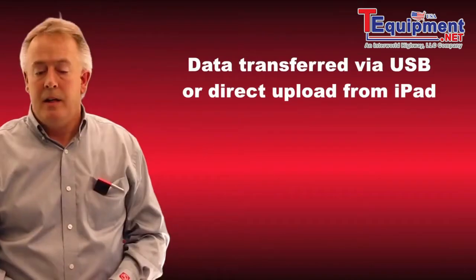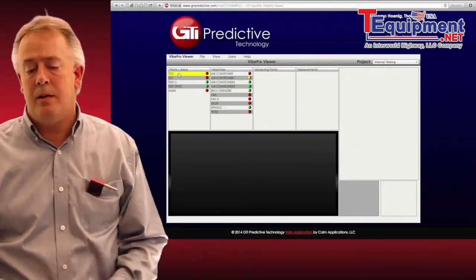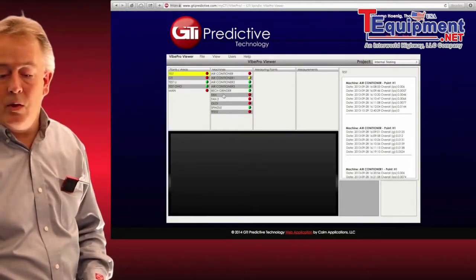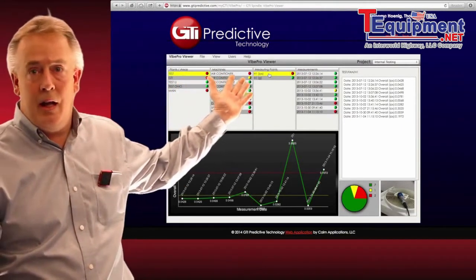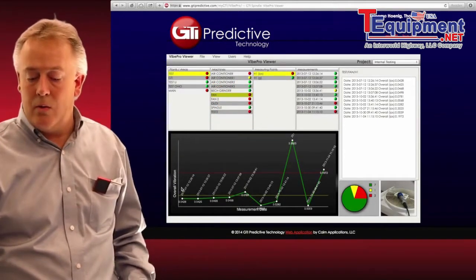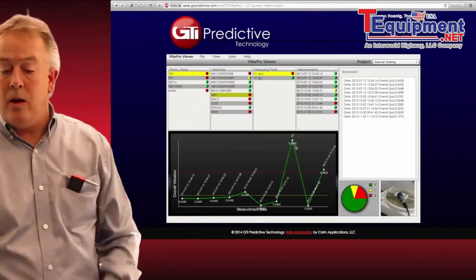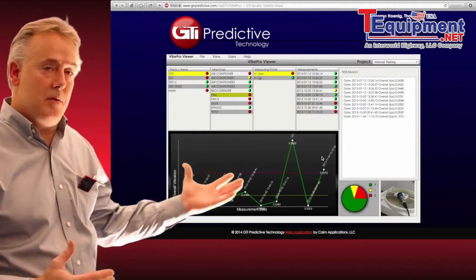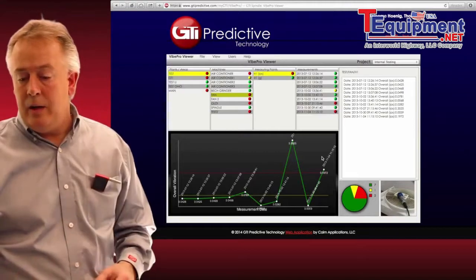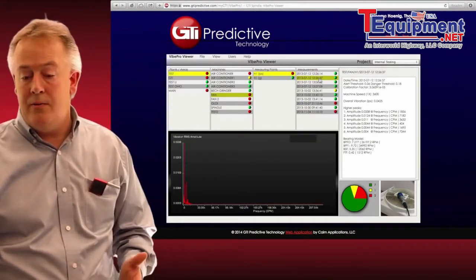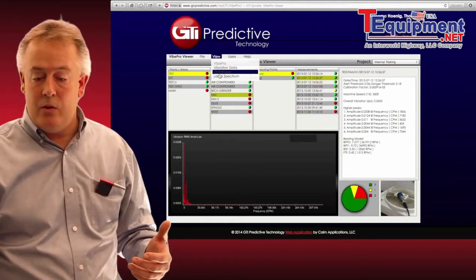Now we're on the second portion of the video — the web app viewer. You'll immediately recognize the same hierarchy. We'll click on the same test point and the same fan, and on that data point you can see immediately the nice trend from before — where it was below the yellow, where it crossed the yellow threshold, where it went above red. There's also a pie chart depicting how many times it went over red, over yellow, and how many times it's been in the green. We can drill down on any particular reading to see the spectrum.